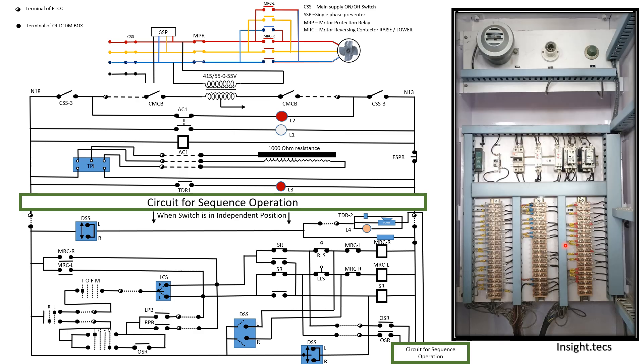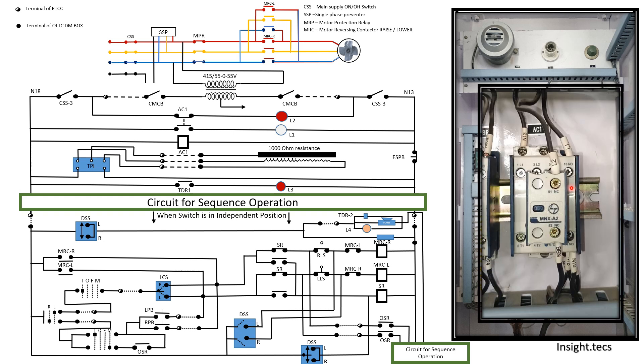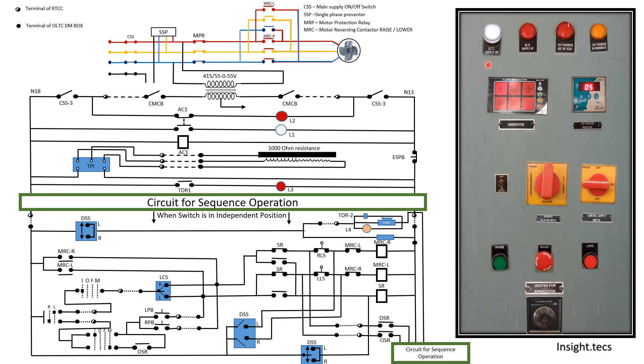Inside the RTCC panel you can see the AC1 contactor. This AC1 contactor is responsible for operating two LEDs located on the RTCC panel. Whenever this contactor is operated and closes, the L1 LED will glow, meaning the RTCC panel supply is on. If it is off, the contactor connects at the other point and the L2 LED will glow. So L1 is for the OLTC supply-on LED, and L2 is for OLTC supply-off.